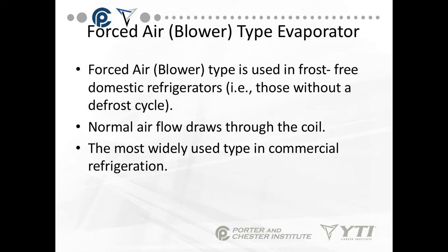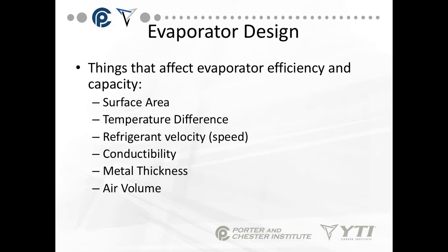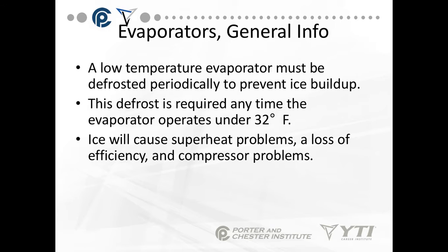The forced air blower type is used in frost-free domestic refrigerators and is also the most widely used type in commercial refrigeration. An evaporator has two purposes: it cools by removing sensible heat, and it dehumidifies by removing latent heat, causing a change of state from vapor to water. Factors affecting evaporator efficiency include surface area, temperature difference, refrigerant speed through the evaporator, metal conductability and thickness, and air volume. A low temperature evaporator must be defrosted periodically — a defrost cycle is required any time the evaporator operates under 32 degrees, not the box temperature.